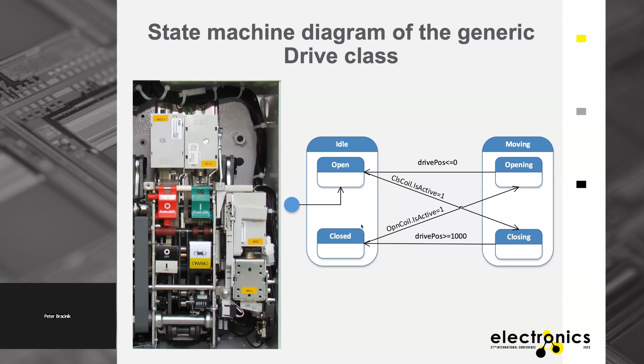So, software capabilities. With this one setup, with the Arduino setup, we can simulate up to 4 disconnectors and 2 circuit breakers. We can simulate adjustable drive speed. It means that we can have different opening and closing times for disconnectors and for circuit breakers, so it will simulate realistic operation times. And we have 2-bit state signalizations, so it will check the status quo of the connection and disconnection of both sides of the contacts. This is something that is used in real life as well.